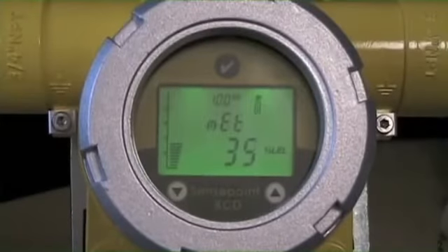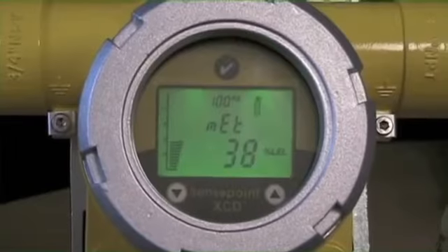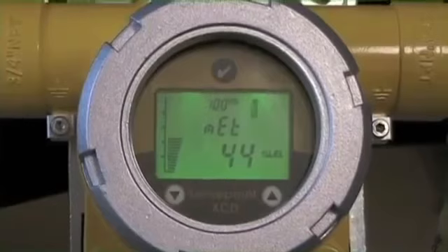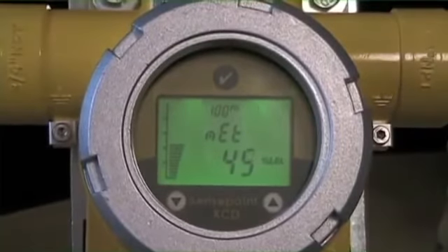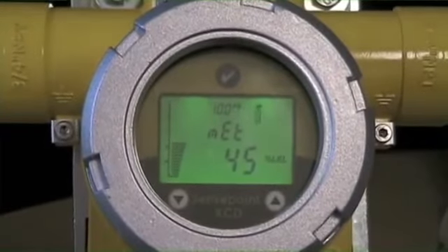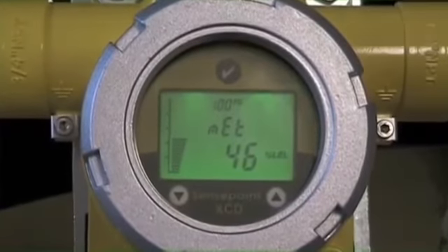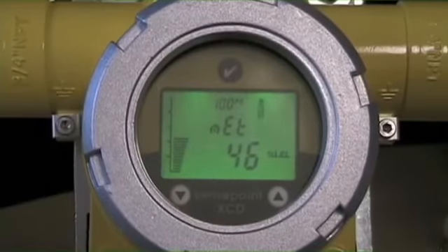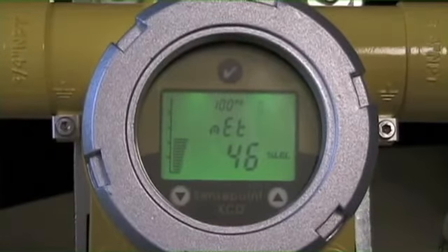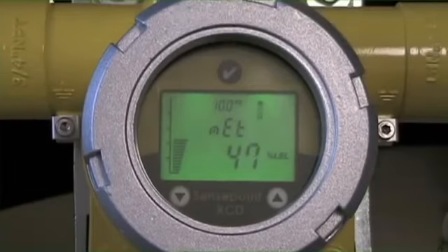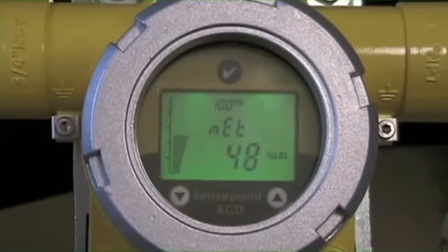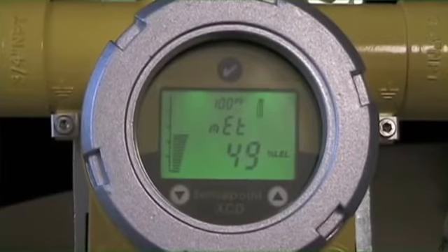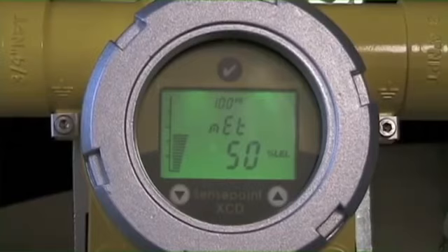I'm going to enter that as my level, and then we're going to go through a process, and I'm going to watch the system as it gets to its value and looking for stable output. So it's going to reach a level, a threshold, and it will stabilize based on its existing calibration information. Once it gets to that stable level, and I'm comfortable that that's an acceptable value, I'm simply going to check mark again, enter that check mark, and that's going to then lock in, give me a pass or fail, but lock in the value and say this is the signal strength that's equivalent to 50% LEL.